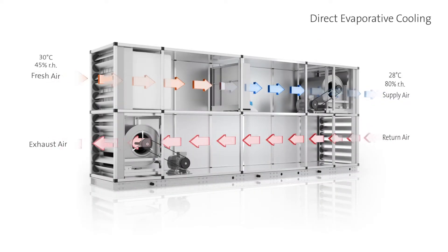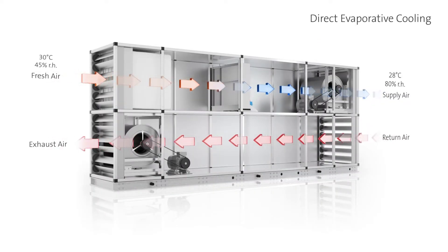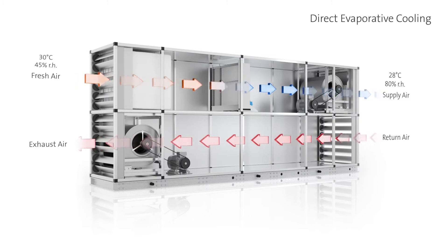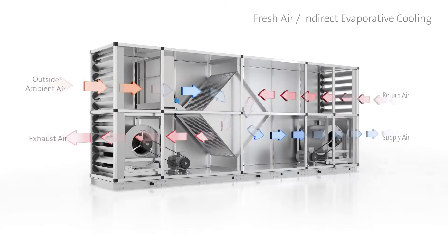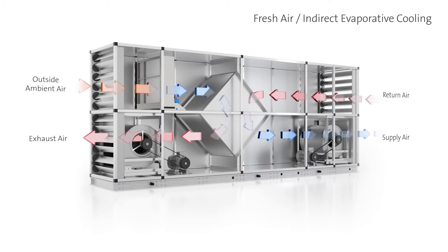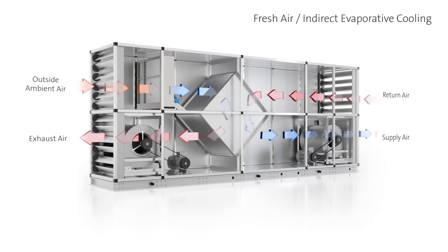Condair adiabatic humidifiers are used in a variety of data center cooling strategies. Direct evaporative cooling raises the humidity of the supply air whilst reducing its temperature. Fresh air indirect evaporative cooling uses the outside air to cool the internal environment via a heat recovery system, without external and internal air streams directly mixing.